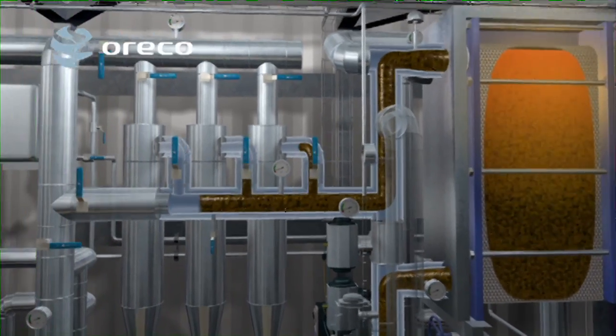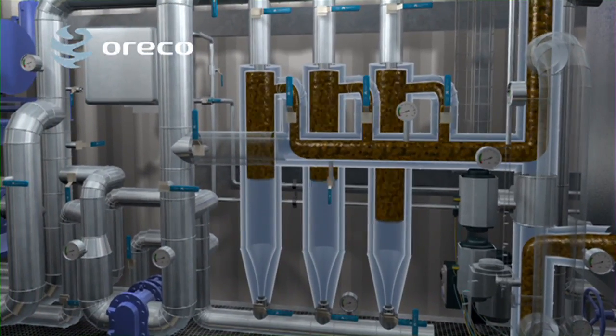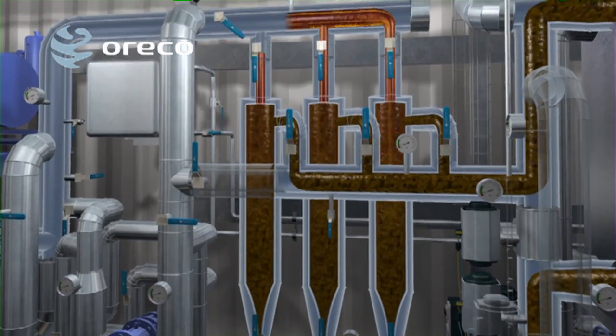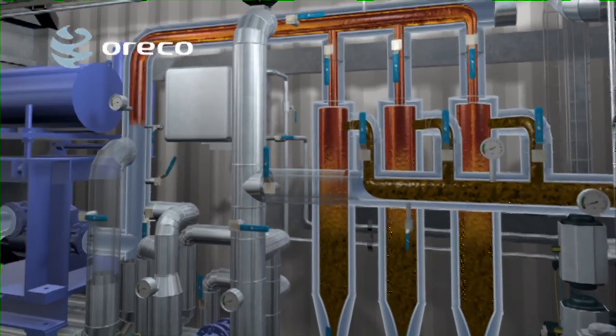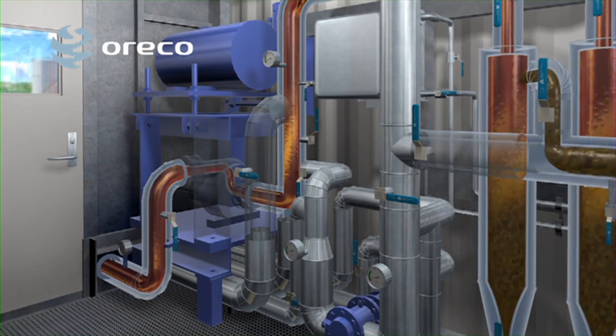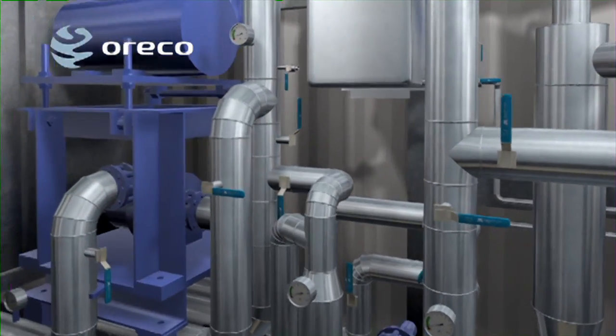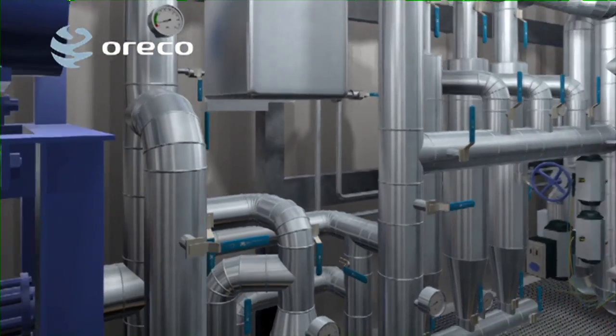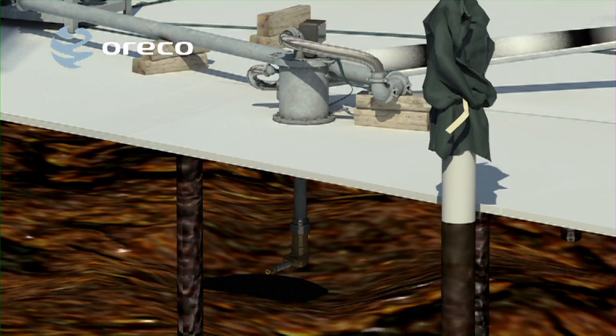From the heat exchanger, the oil is led to the hydrocyclones to separate heavy solid particles from the recirculating cleaning media. A booster pump returns the cleaner fraction to the storage tank, where it is used to reliquify more sludge. The recirculation loop is complete.